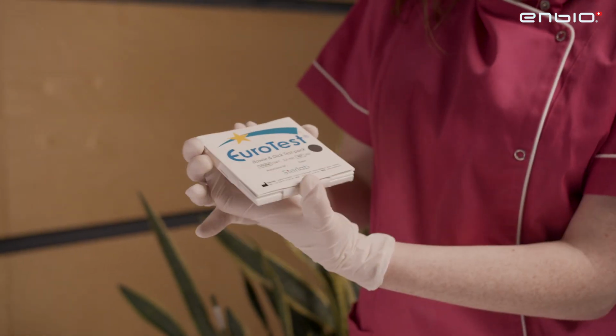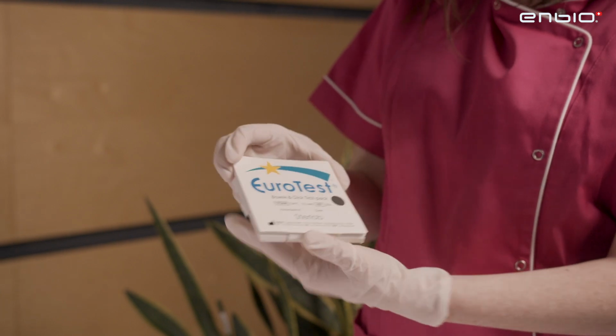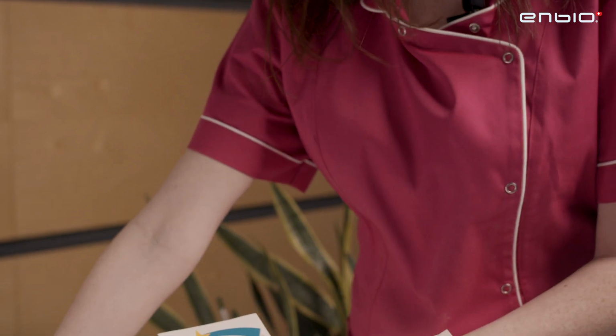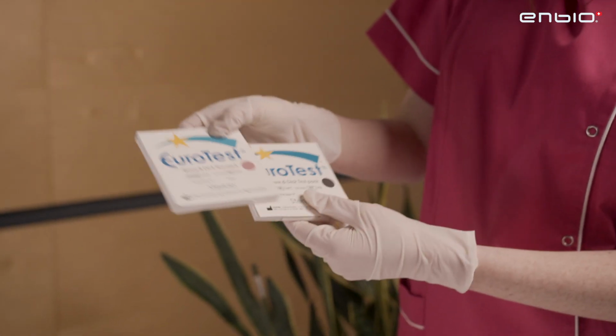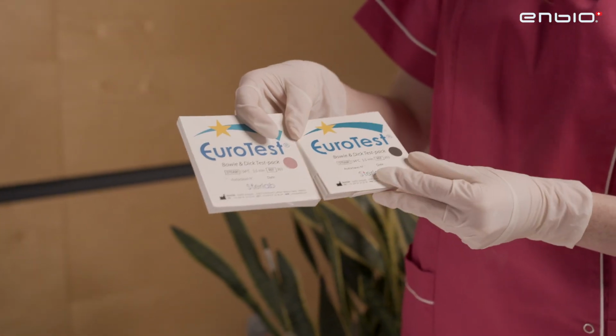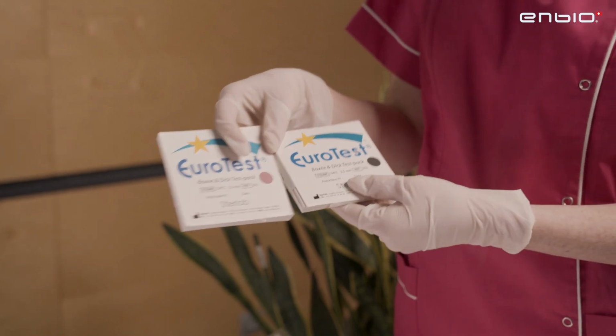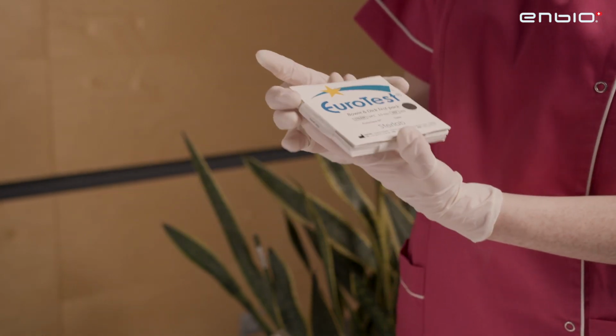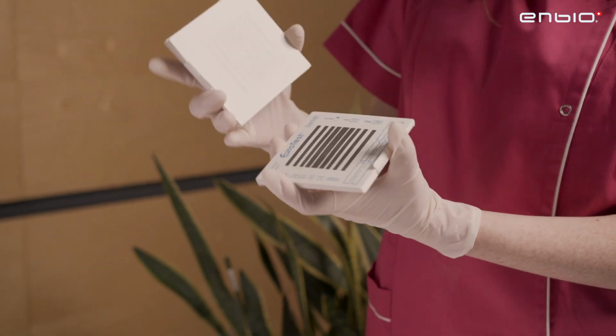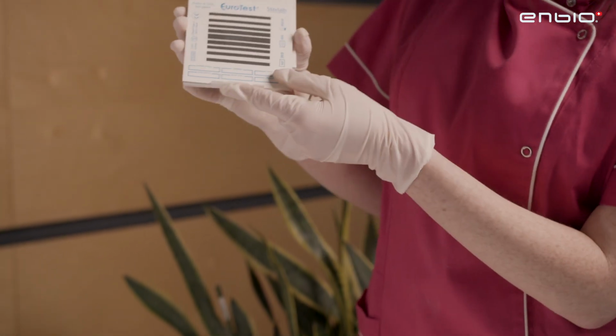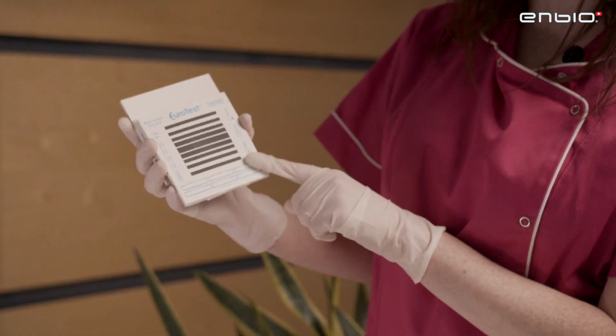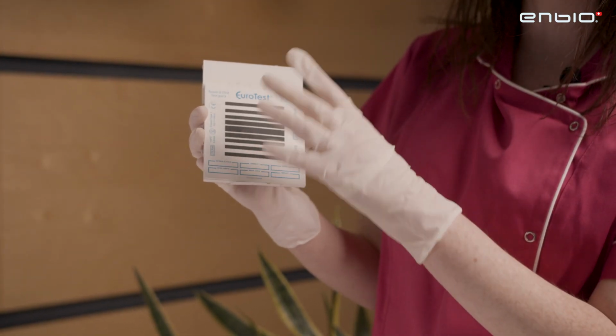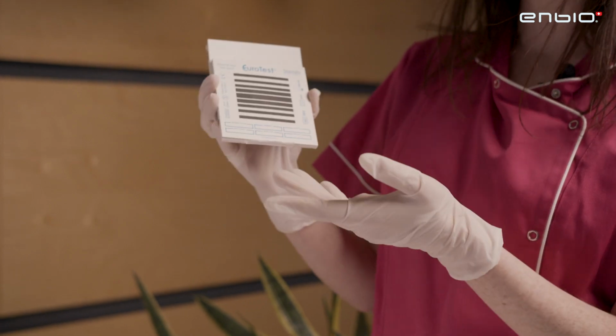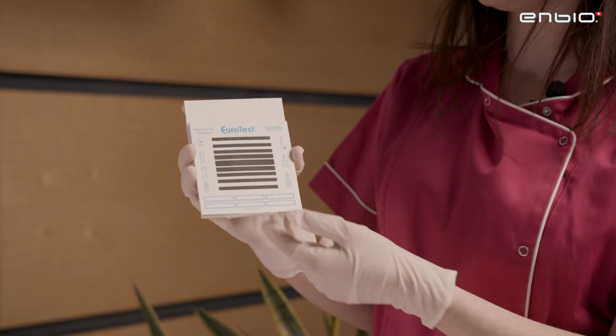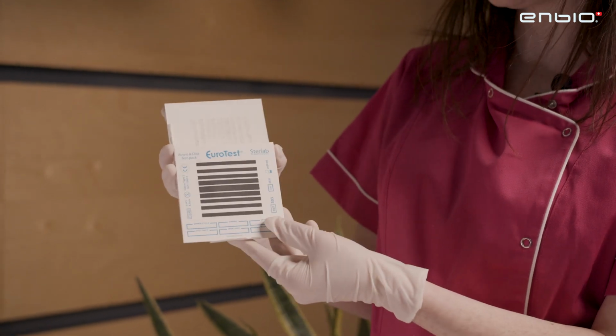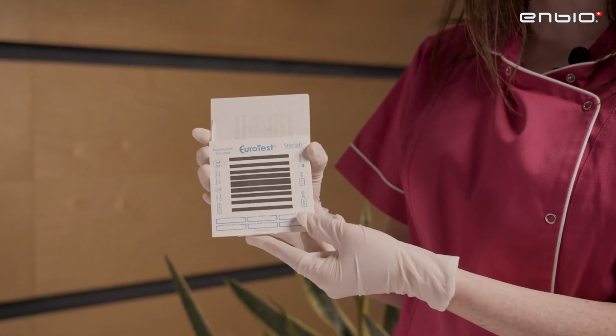So for instance, to check the results of the Bowie and Dick test, first of all, we will see that the color on the surface of the test changed from pink to black. And then, very important, we have to open the test and see inside of it, in the middle of it, we have these lines. And if all the lines are black without any white stains, it means that the steam penetrates perfectly within the autoclave and the sterilization is done properly.